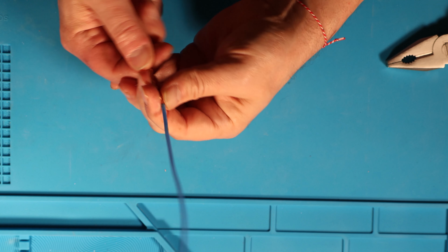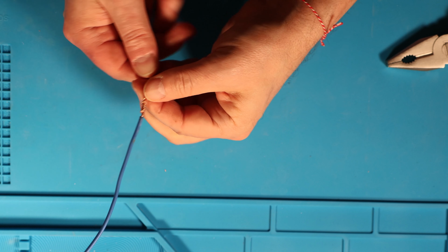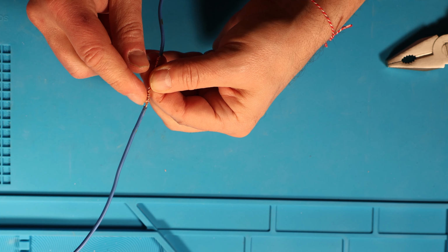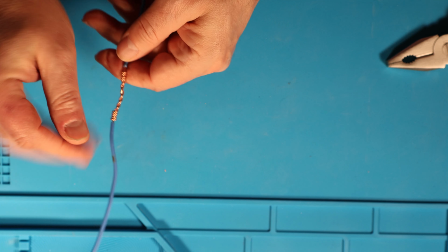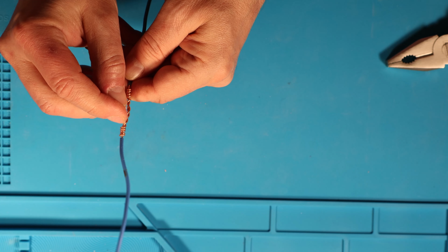You can see any sort of these too. Here, for certain, the bending radius is much smaller than the minimal one. Very, very wrong as well. Never forget about the minimal bending radius, guys. And always use this knowledge when assessing new and amazingly successful new ways of connecting wires and laying down cables in buildings. Results could be devastating.